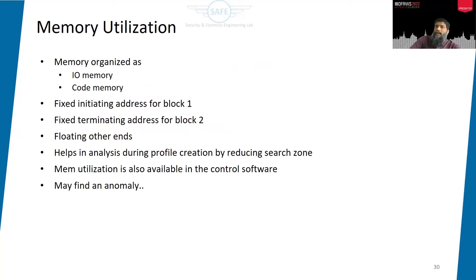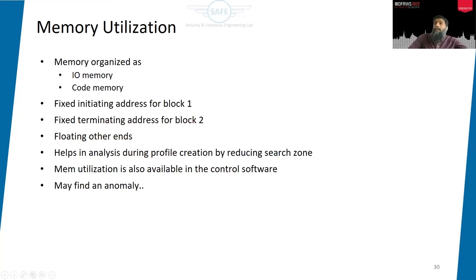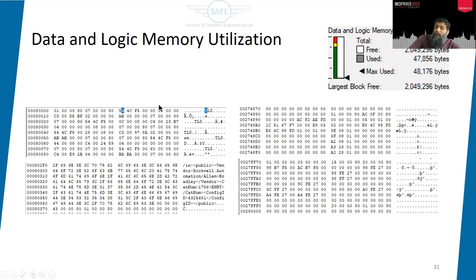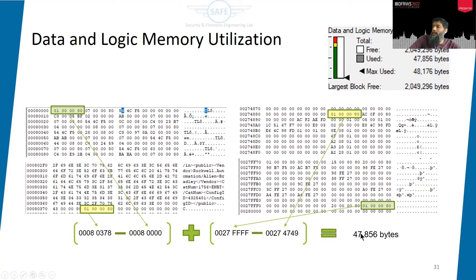Coming to memory utilization: there are two memories, and the data and logic memory has two blocks. Block one always starts at a fixed address — around address 0x00080000 — and floats at the end, so the ending address for block one is variable. For block two, the ending address is fixed but the starting address floats. These values exactly match what is available in the control software. So if the user expects something different from what the memory dump shows, we know there is a problem.